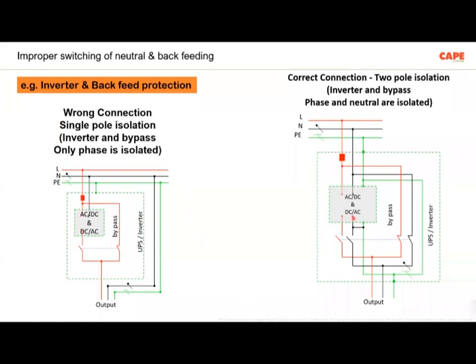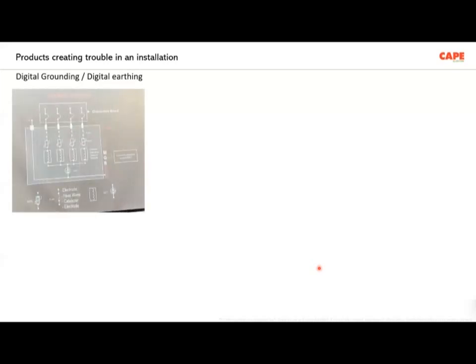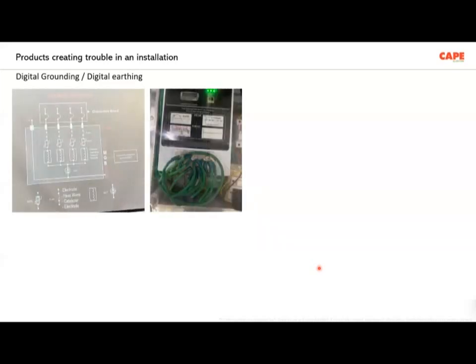So, while using inverters, please ensure that the requirement on the right side, which I am showing, is met: both the phase and the neutral must be isolated. Inverter or UPS circuits shall have the phase and the neutral segregated from other parts of the wiring. But unfortunately, an inverter with 2-pole isolation is quite rare in the market. We have to really search for it. So rather, I would make a statement that we actually use products which are inviting fire rather than protection.